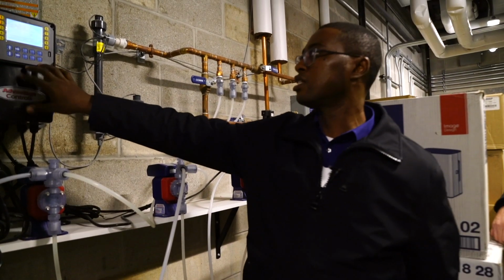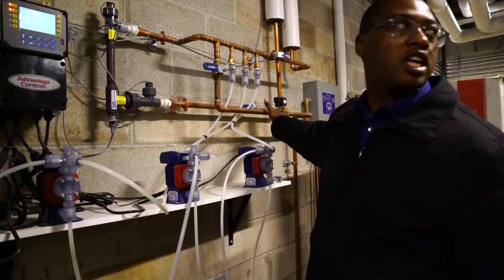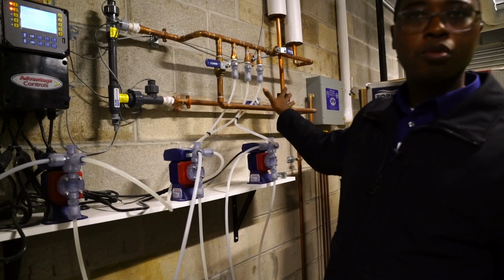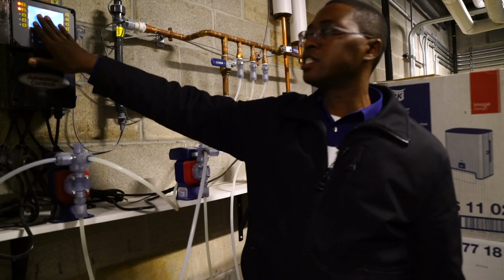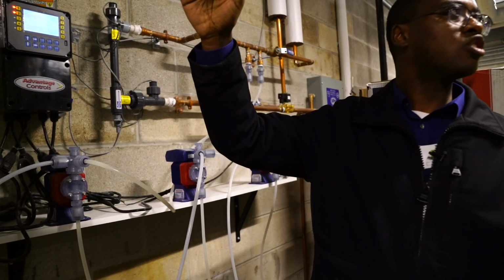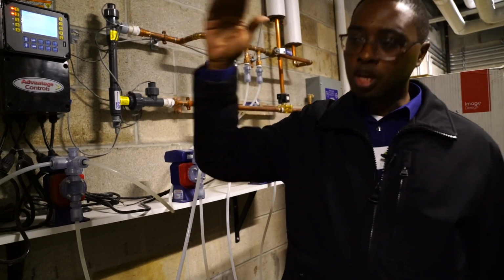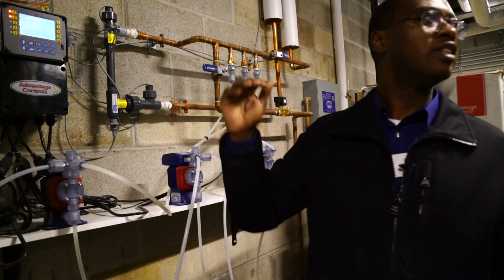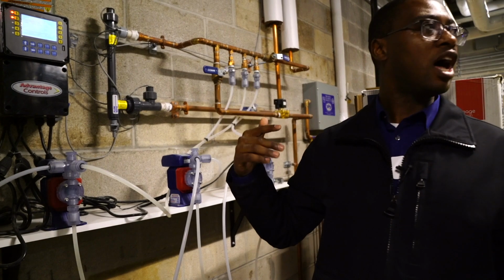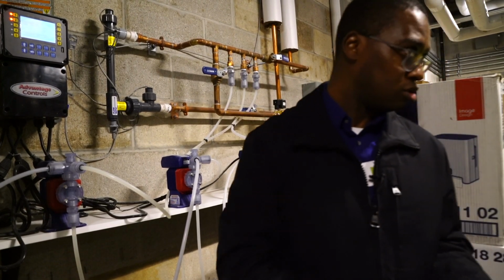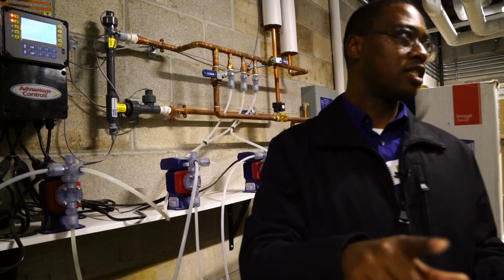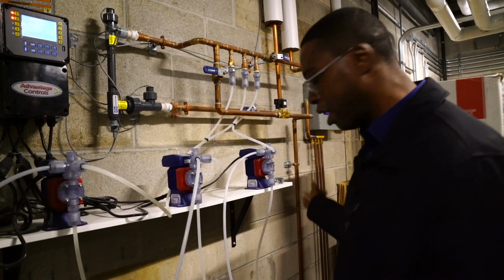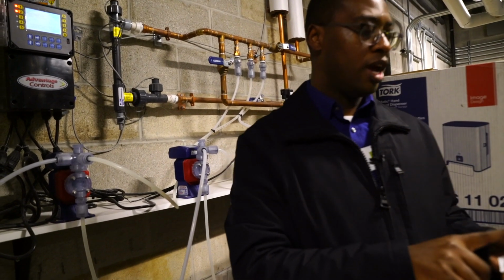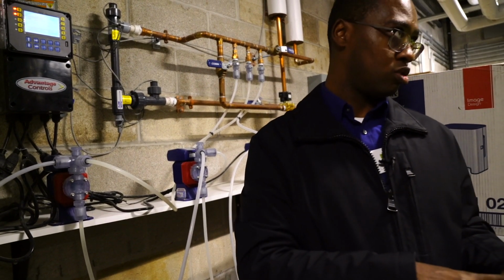This tells this valve, which is a normally closed valve, energized by this controller, hey, we got to our number, which is 1,200, our set point, you've got to blow down. And then it blows down. When it blows down, that's how you lose chemicals. It goes to a sanitary drain, so this should be piped straight to your sanitary drain. And then there are also 2 ways you lose water in your tower.